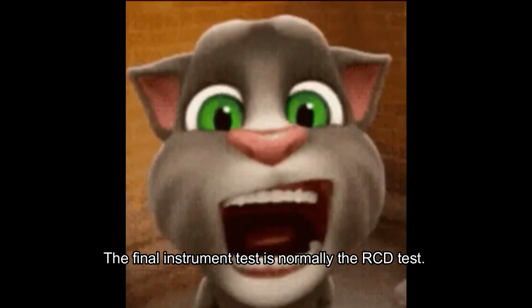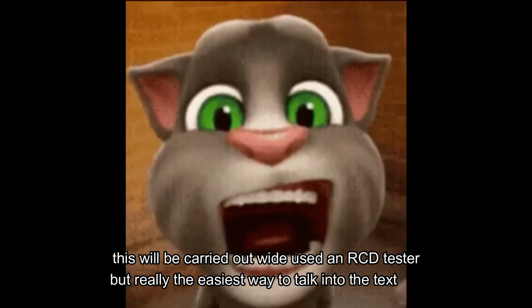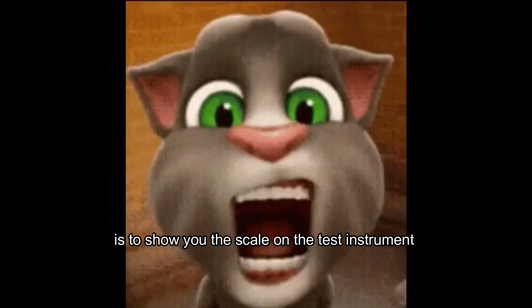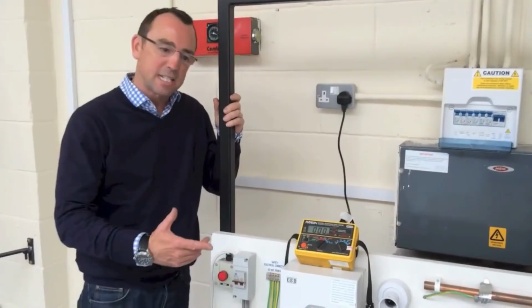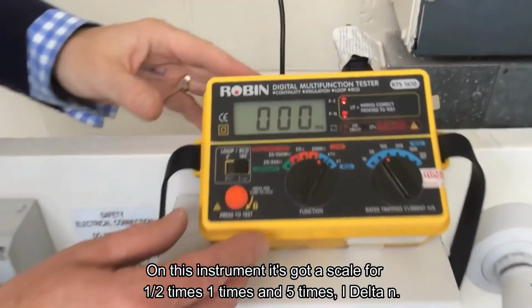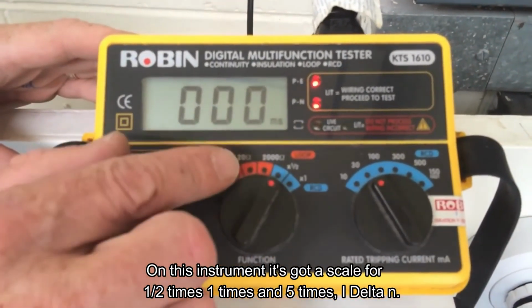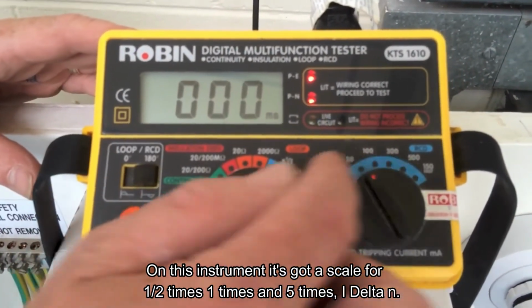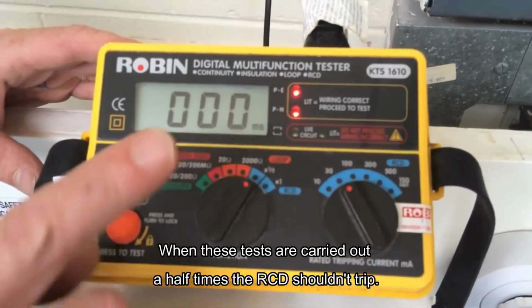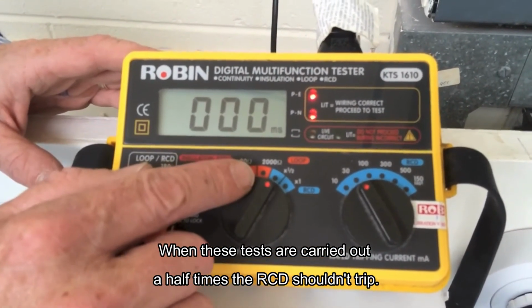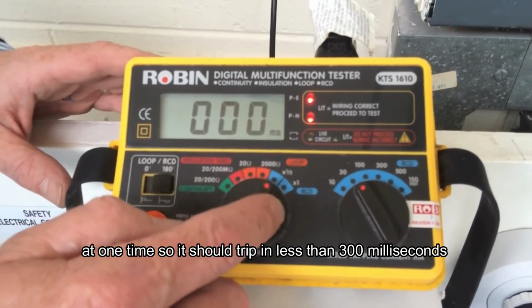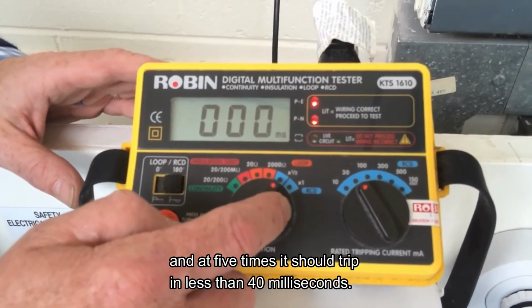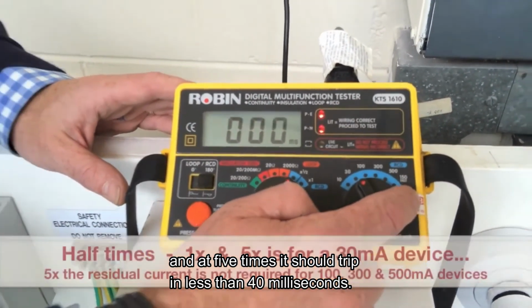The final instrument test is normally the RCD test. This will be carried out using an RCD tester, but really the easiest way to talk through the test is to show you the scale on the test instrument. On this instrument, it's got a scale for half times, 1 times, and 5 times I delta n. These tests are carried out at half times. The RCD shouldn't trip. At 1 time, it should trip in less than 300 milliseconds, and at 5 times, it should trip in less than 40 milliseconds.